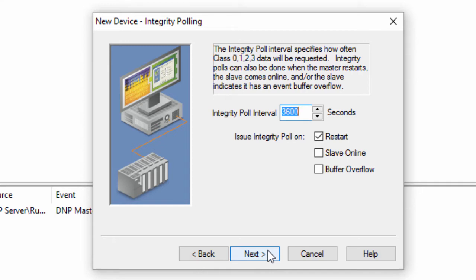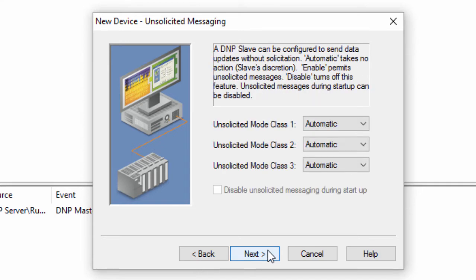Click Next to specify whether or not to enable unsolicited messaging. The DNP protocol allows the slave to update the master with data changes without a poll from the master. This is fully controlled by the slave and most slaves allow you to configure any delays or item deadbands for unsolicited messages.